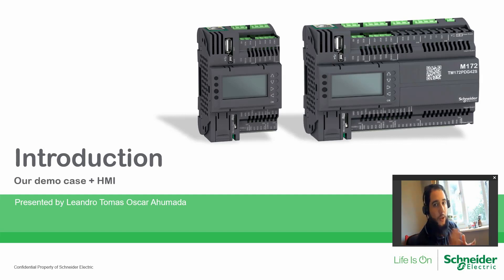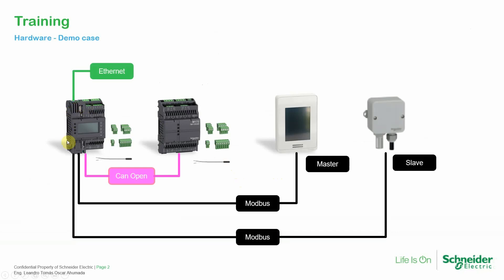First, let's go back to our demo case and see how we can communicate that demo case with one HMI. In our demo case we already have the PLC, the expansion module, the remote display the M172D, and our temperature and humidity sensor. The humidity sensor is connected via Modbus to the PLC, where the PLC is the master and the device is a slave.